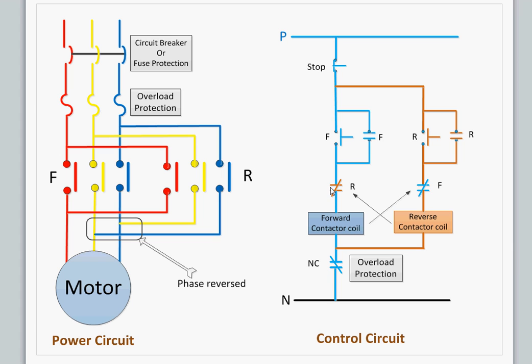There are normally closed contacts of the reverse contactor and the overload protection. The forward contactor will operate, and this is the hold-on contact of the forward side. After the push button is released, current keeps flowing through this hold-on contact.